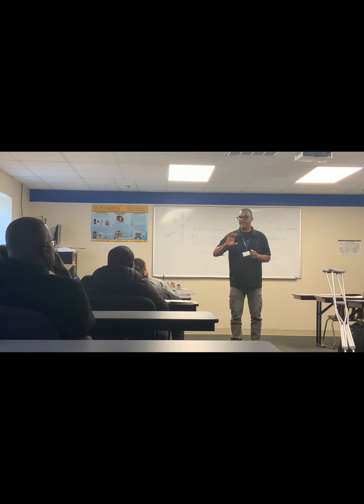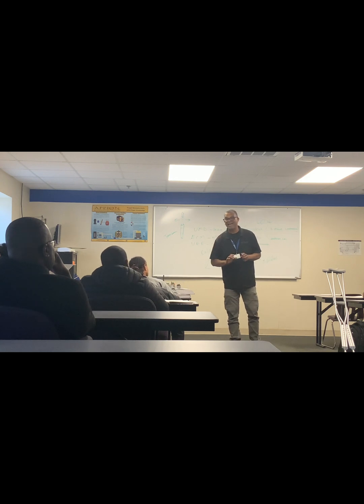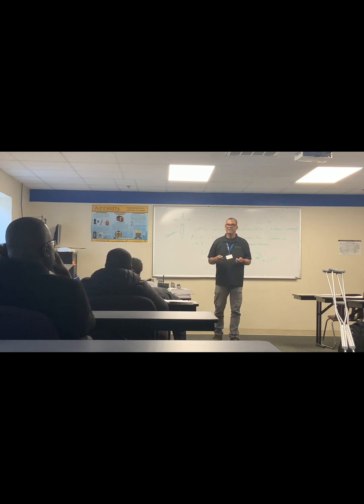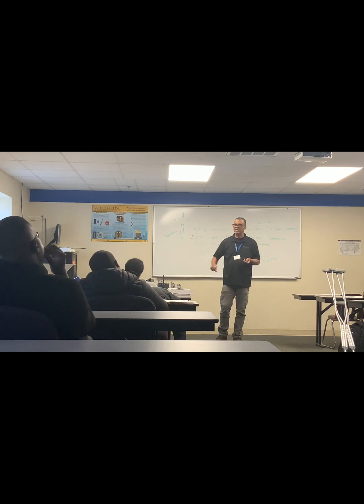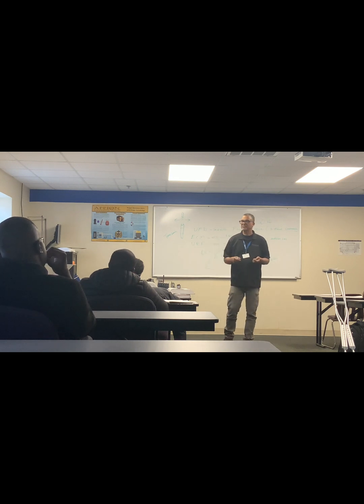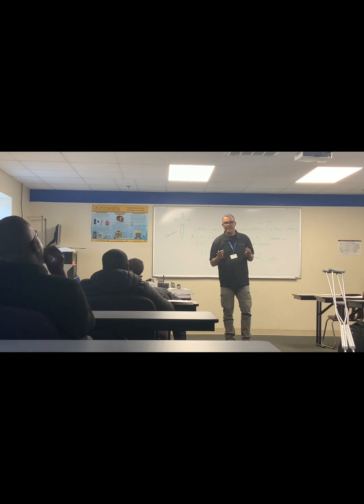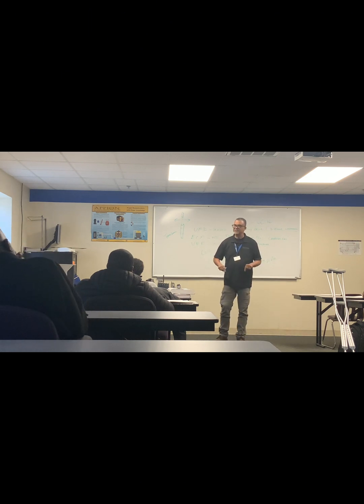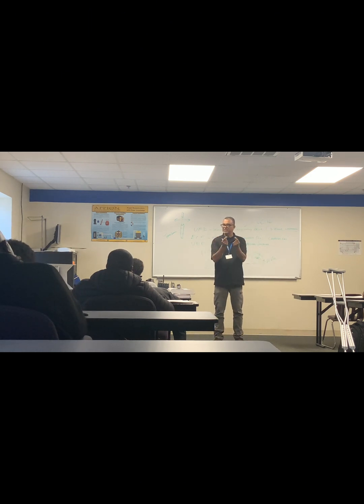And if you did it by hand, you would say, oh, that's too loose, but it's really not. There's actually a one-day school on tension of belts, because it's that important. Some people have belts hanging all on systems and they change them constantly. They just keep putting them on. Never tighten a pulley, and a belt must ride at a certain level in a pulley. It can't be digging all in the creases. It has to ride lip to lip on top to pull or to slip.